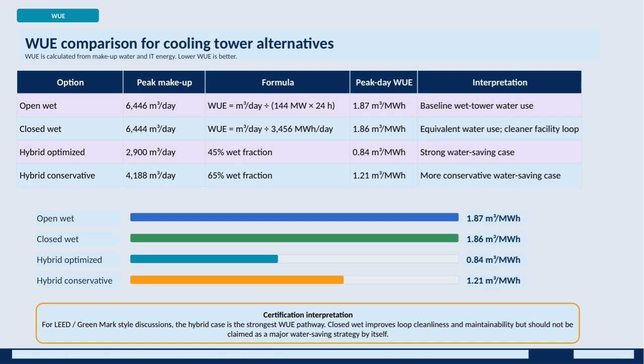While the water savings here are minimal, the closed wet system improves loop cleanliness and makes maintenance easier. The hybrid options present more significant water savings. The hybrid optimized system uses only 2,900 cubic meters per day, cutting the WUE down to 0.84. This represents a strong case for water conservation, making it the most efficient option in terms of water use.